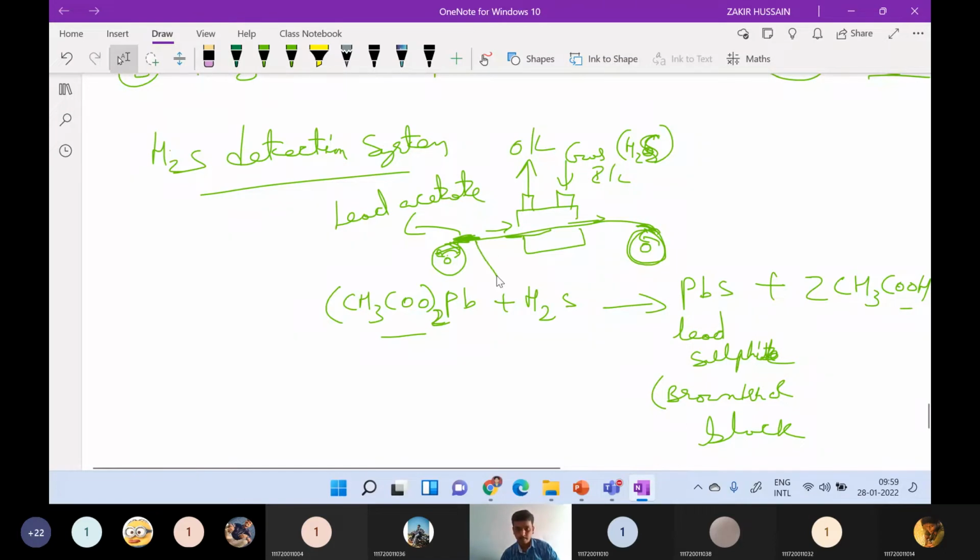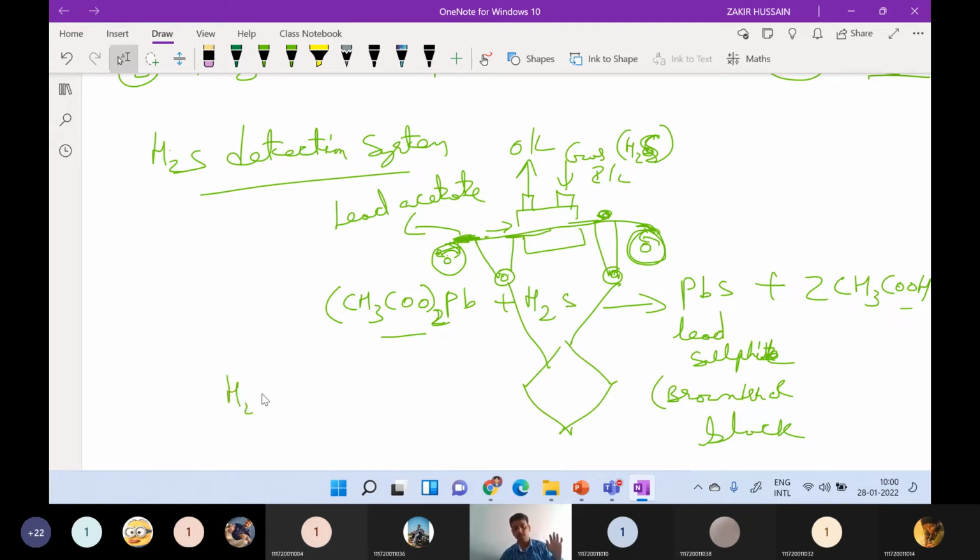So to calculate the reflectance, photo tubes will be connected. Commonly, the photo tubes will be connected to a Wheatstone or Callendar bridge circuit. Therefore, the decrease in the reflection from the starting to the ending point will be compared, and the corresponding value of the amount of H2S present in the system is directly proportional to the decrease in the reflectance of the particular tape.